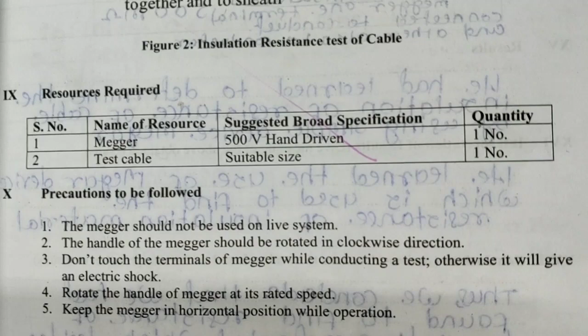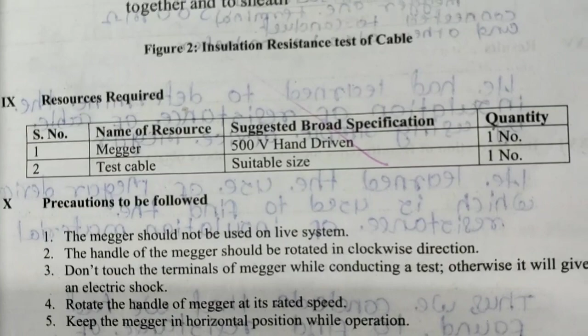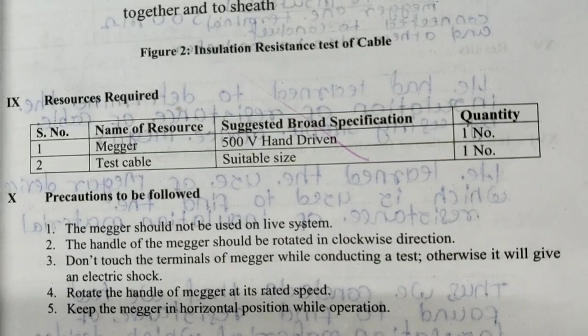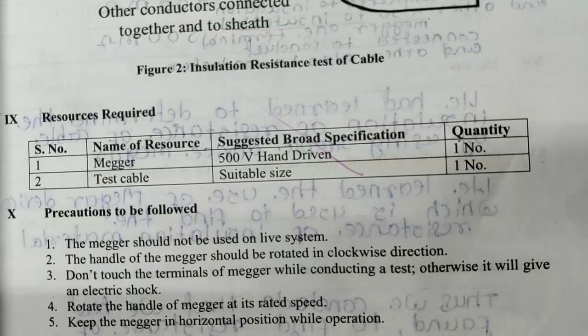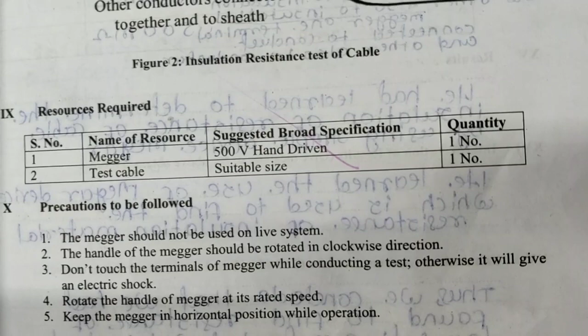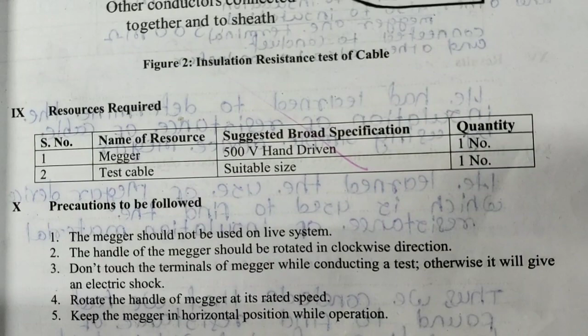Don't touch the terminals of the Megger while conducting the test, otherwise it will give you an electric shock. Means whenever you connect the test terminals of the Megger and rotate its generator, its spindle handle, then don't touch any contact. If you touch the contact, you will get a shock because 500 volt is generated at the terminal. Rotate the handle of the Megger at its rated speed.